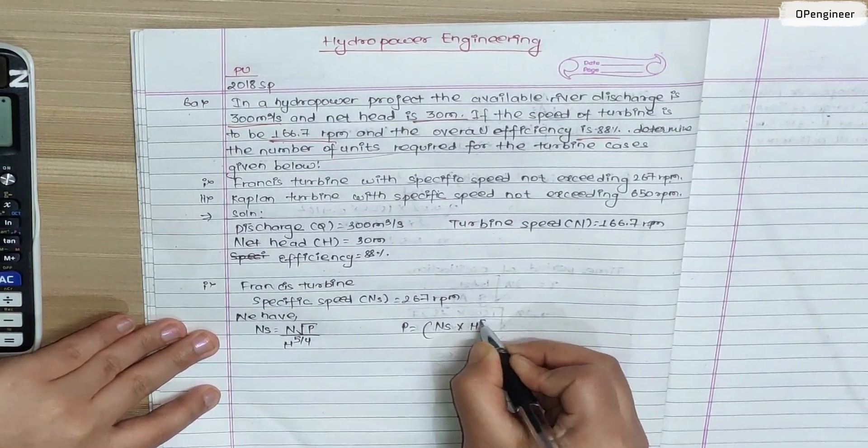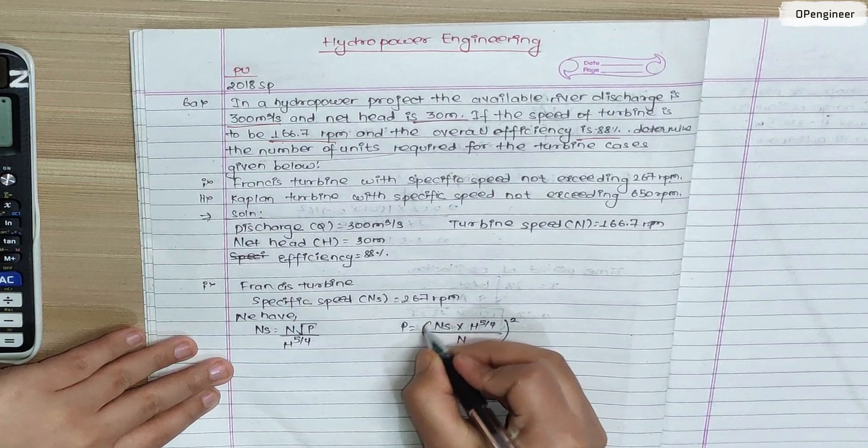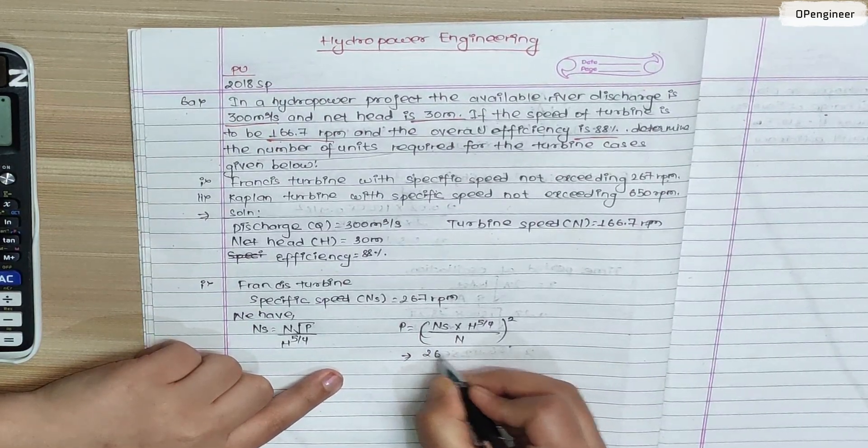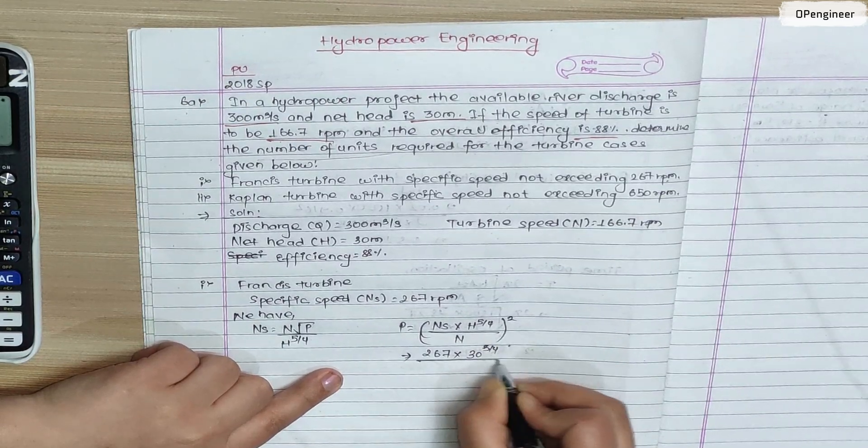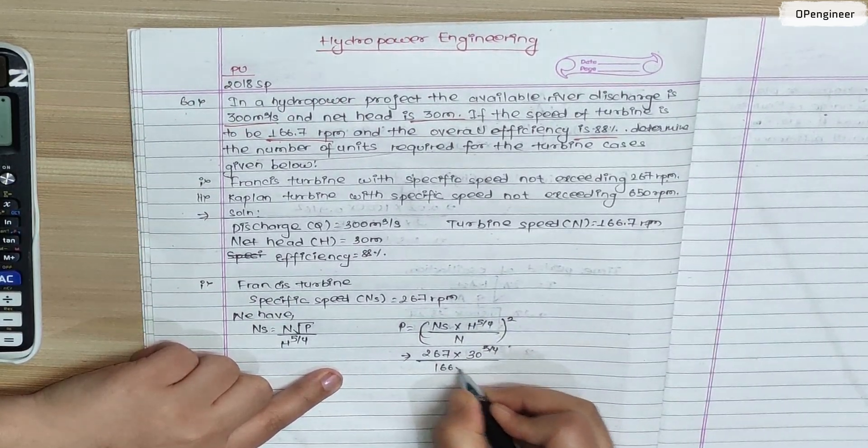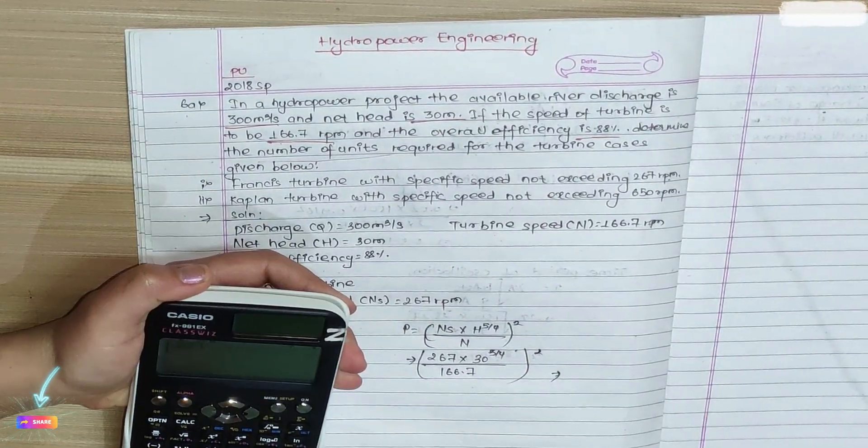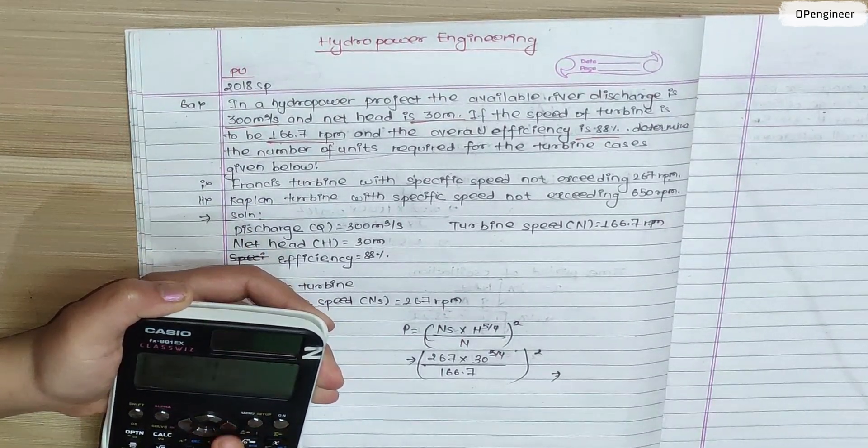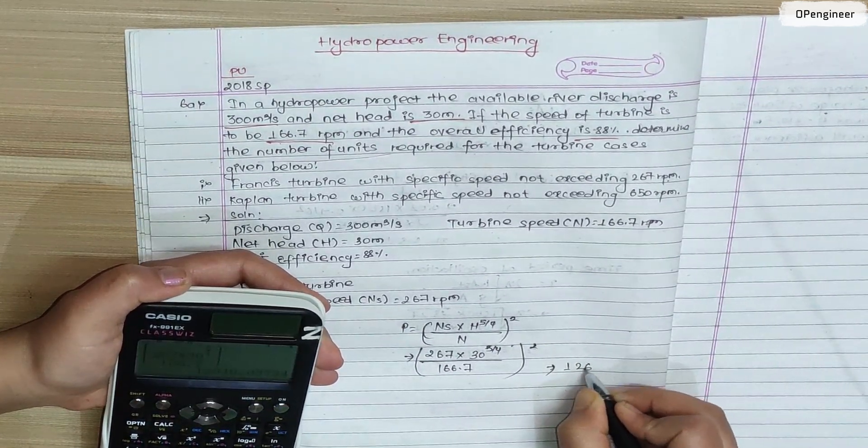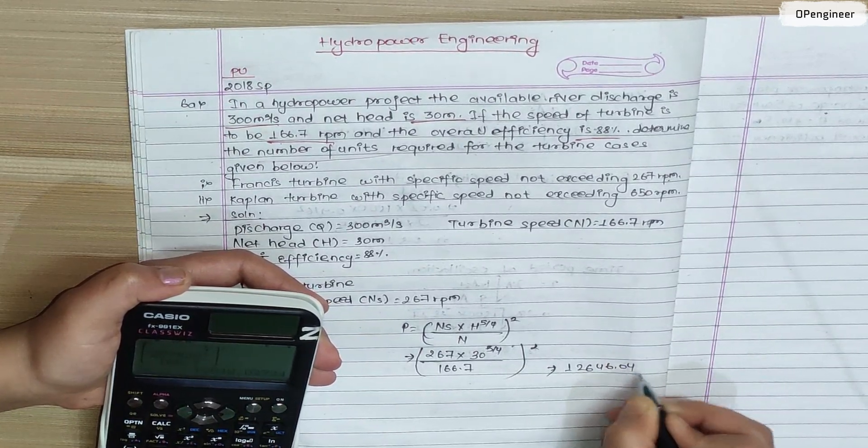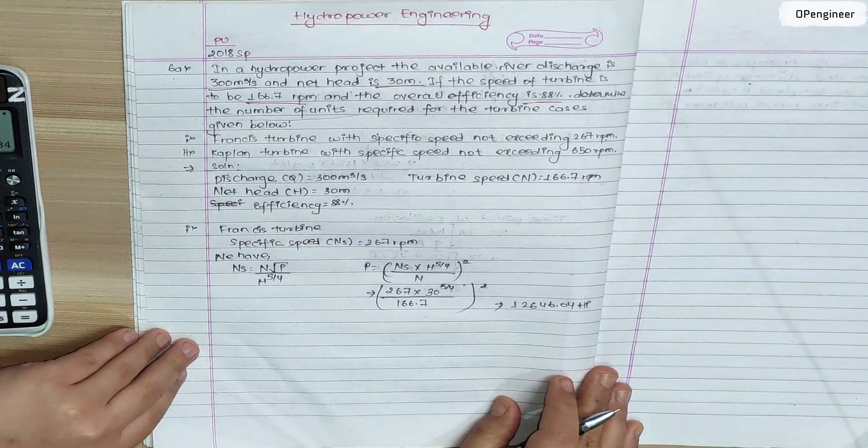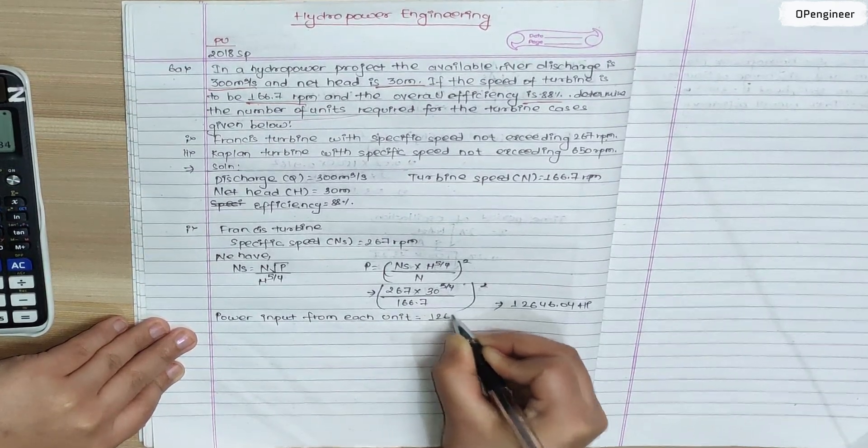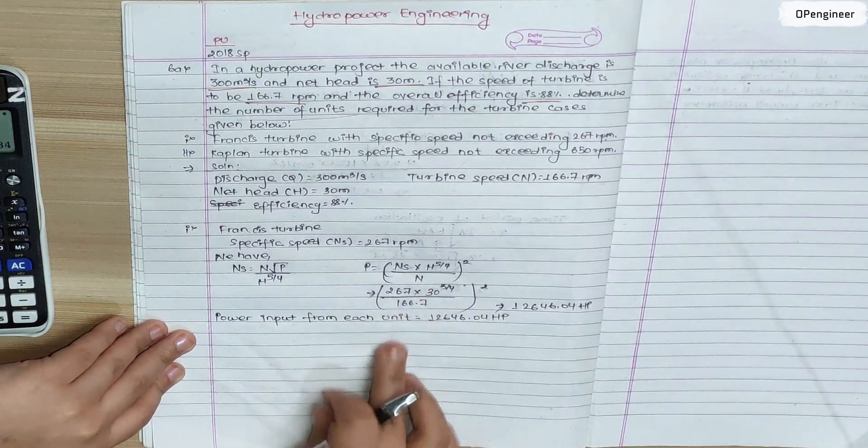The formula is Ns = N times square root of P divided by H to the power 5 by 4. So 267 = 166.7 times square root of P divided by 30 to the power 5 by 4. Calculating this: 267 into 30 power 5 by 4 divided by 166.7 whole square equals 12646.04 horsepower. This is the power input from each unit.